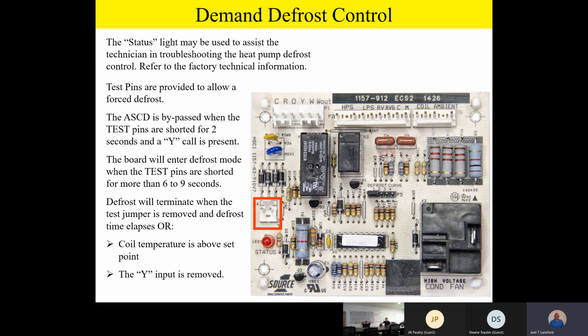So let's talk about those test jumpers a little bit more. If I hold those test jumpers for 2 seconds and I have a Y call, in other words, if I've got a Y call from the thermostat for compressor operation, and I hold those pins, that jumper, for 2 seconds, it's going to bypass the anti-short cycle timer for servicing. Now, please note, if you jumper those test pins for less than 2 seconds, nothing happens.